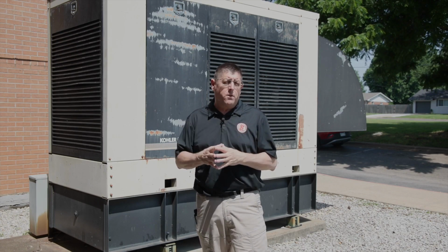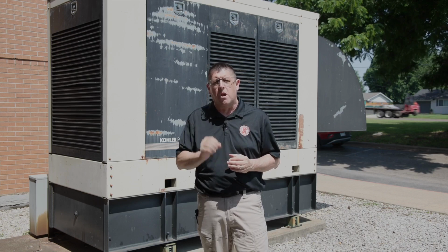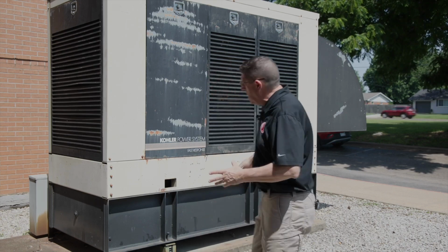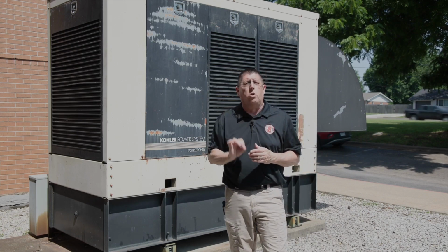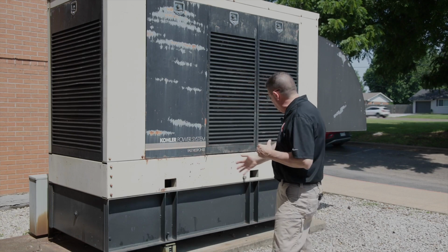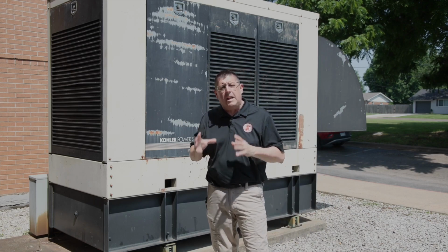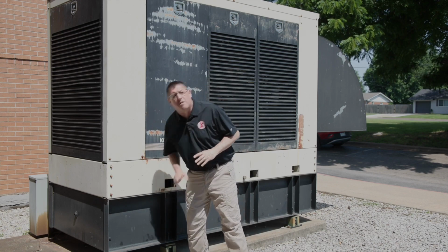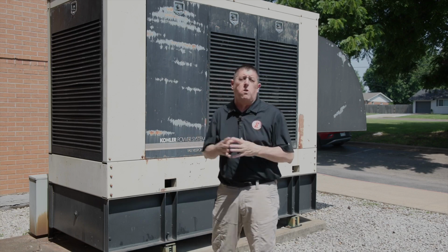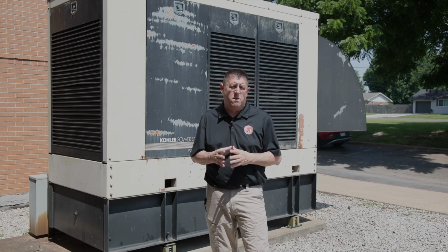But there are a few things you can, as a proficient commercial property inspector, look at. For instance, when I look at the outside generator, especially those with fuel oil, I'm going to take a general view of the outside of it and look for leakage. Any leakage of that fuel oil, which is located down here in this basin, would certainly be a situation that your client's going to want to know of.